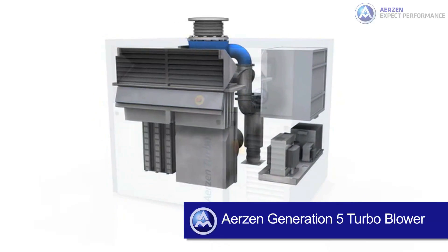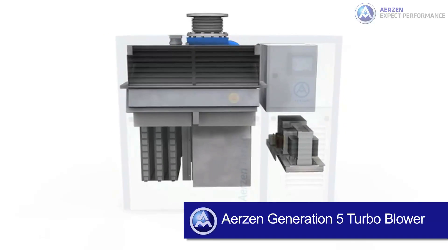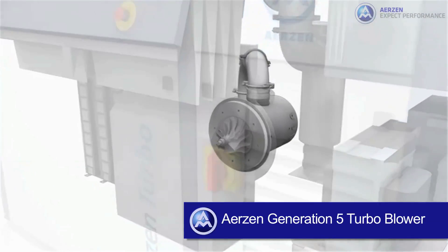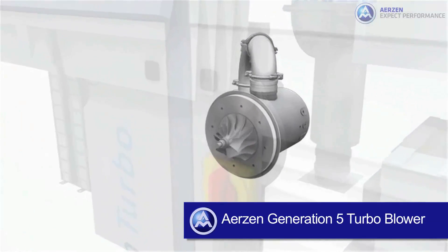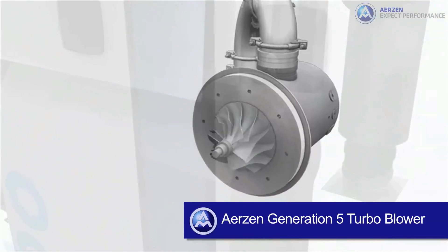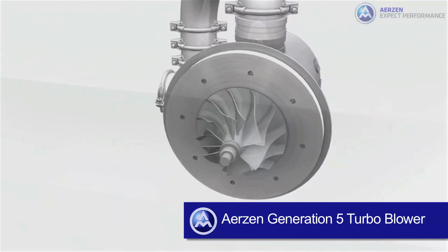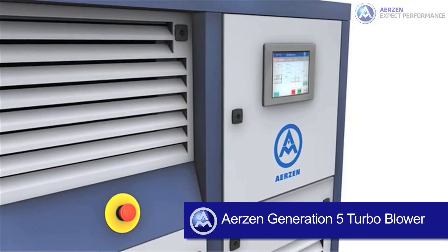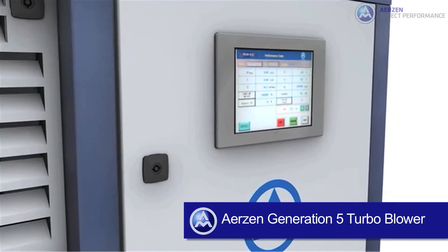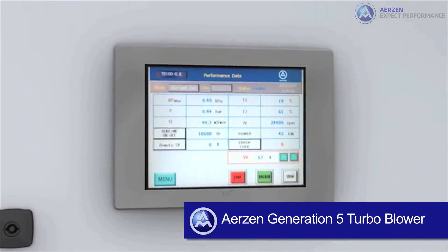The enclosure allows side-by-side installation and includes an intuitive user interface. The Aerzen Turbo Blower features a stainless steel impeller driven by a permanent magnet motor, which produces very high aerodynamic and drive efficiency, rotating in excess of 30,000 RPMs. The rotor assembly is supported by an aerodynamic contactless bearing, which adds to the high efficiency of the machine while providing oil and maintenance-free operation.